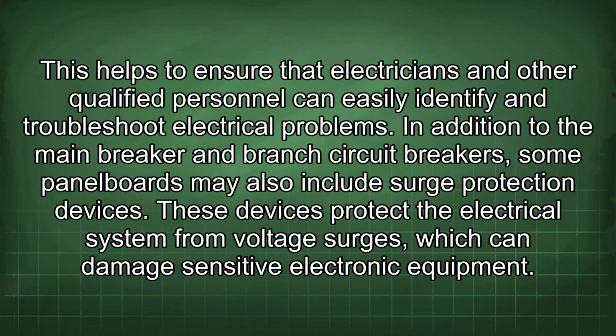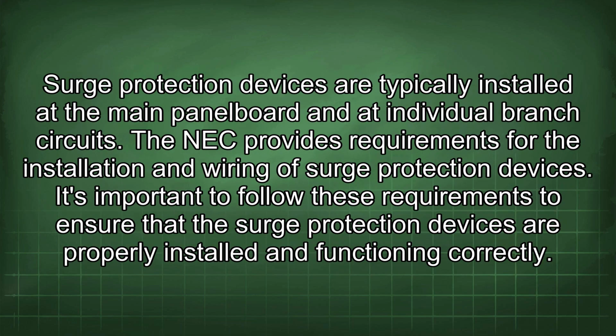In addition to the main breaker and branch circuit breakers, some panel boards may also include surge protection devices. These devices protect the electrical system from voltage surges, which can damage sensitive electronic equipment. Surge protection devices are typically installed at the main panel board and at individual branch circuits. The NEC provides requirements for the installation and wiring of surge protection devices. It's important to follow these requirements to ensure that the surge protection devices are properly installed and functioning correctly.